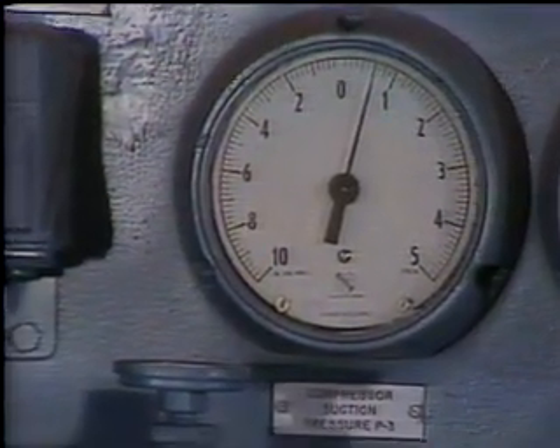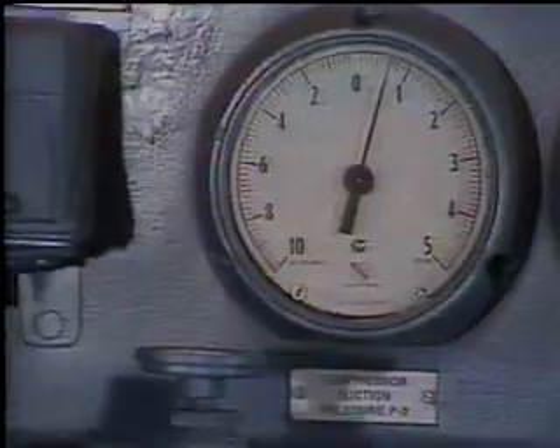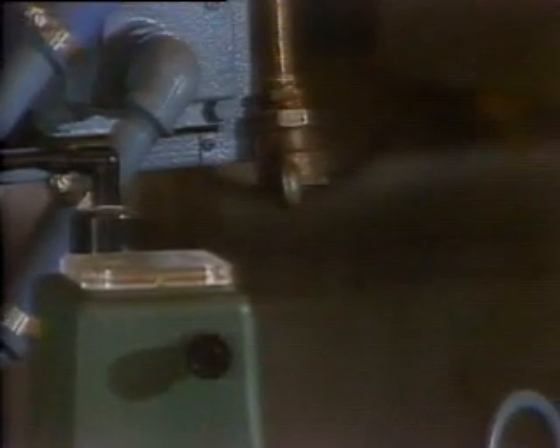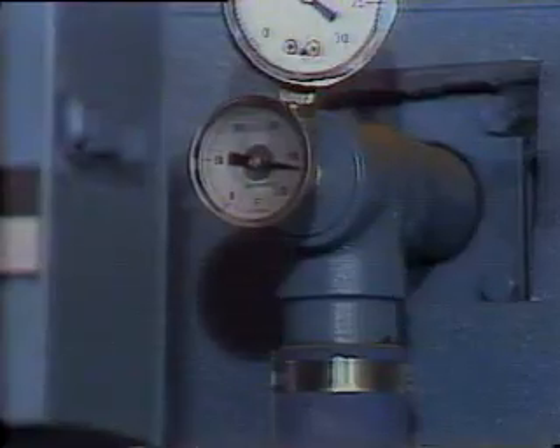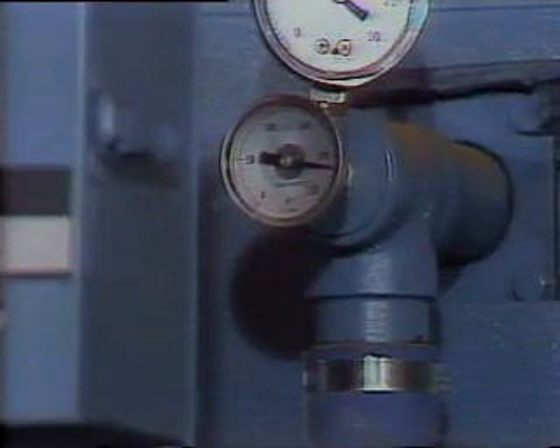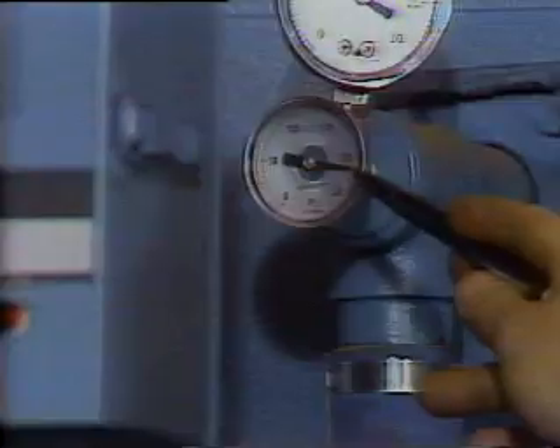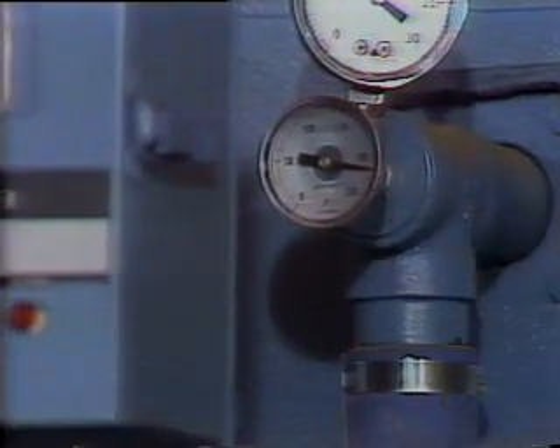Once the compressor suction pressure reaches 0.5 to 1.0 psig, you're about ready to start the unit up. You'll get steam out of the steam chest vent valve, and the recirc thermometer will be about 214 to 215 degrees Fahrenheit. Don't wait too long or all of the water will boil out of the boiler.